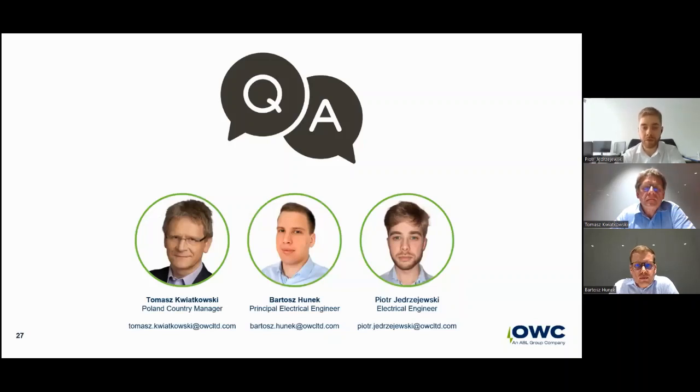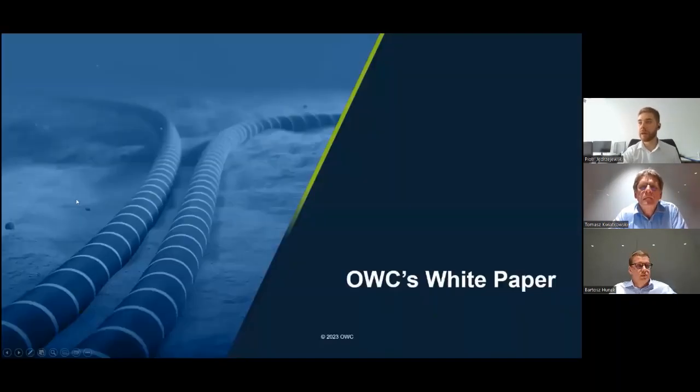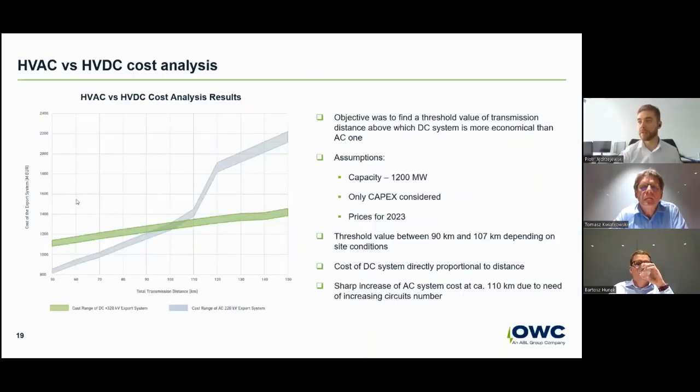Okay, so the question is, do you think that HVDC will be the best technology for export for Site 60E, although it's so expensive? Maybe I'll explain it. We're going back to the cost slide as we talk about the expensive cost of the project. I feel that yes, this technology would be prevailing. It's at the moment rather a gut feeling than some deep, site-specific analysis with a lot of considerations, which may be different than the model that we performed here. But the projects in the area of 60E are all about 100 to 110 kilometers, with maybe some changes due to cable routes.